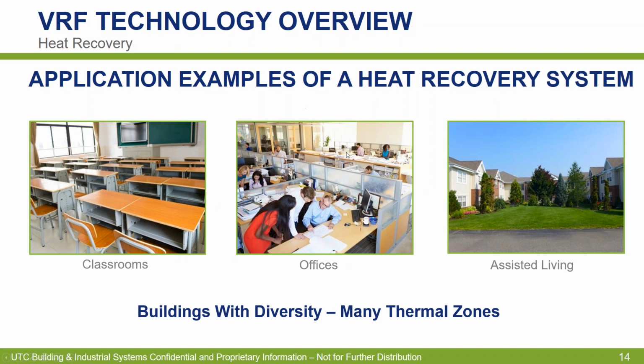Applications for heat recovery systems: classrooms, offices, assisted living, right? This is where we have typically a bunch of smaller zones, different exposures. So you might very well have a room on the east side of the building, huge solar gain, they're going to want cooling in the morning, right? Well, you've got another room on the flip side, west side of the building, that could very well be calling for heat first thing in the morning. Good application there for heat recovery.